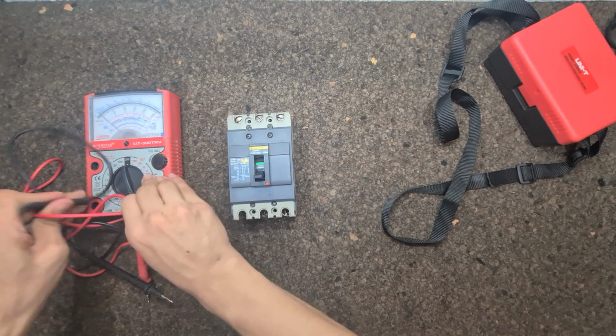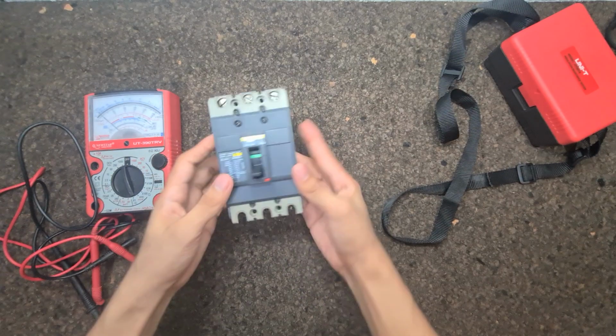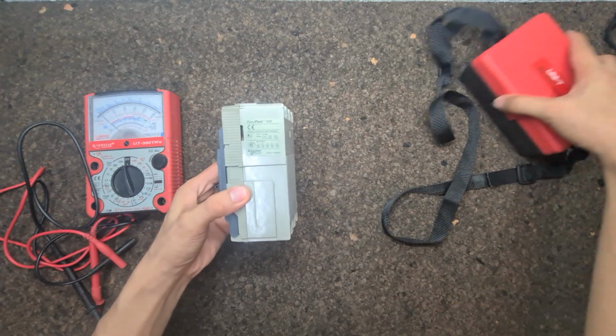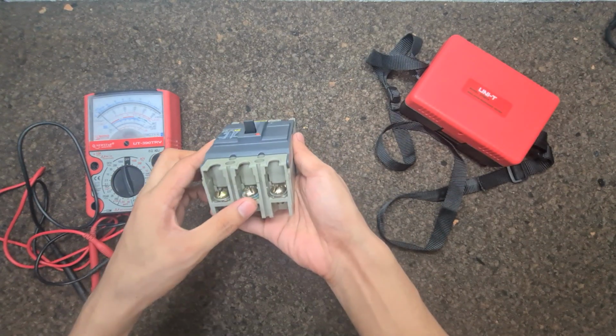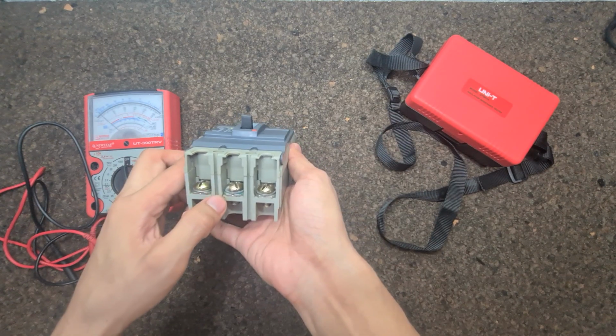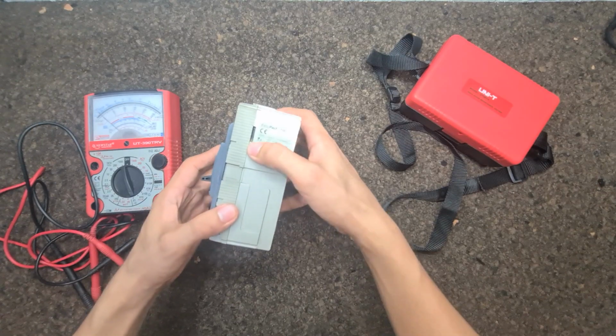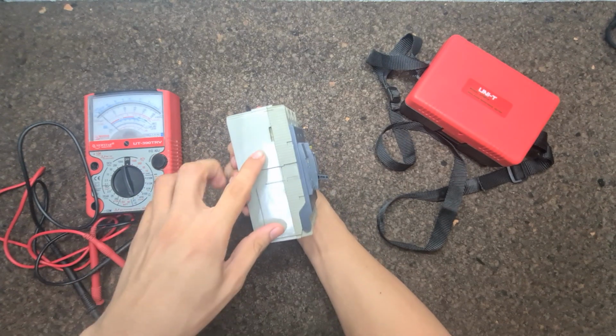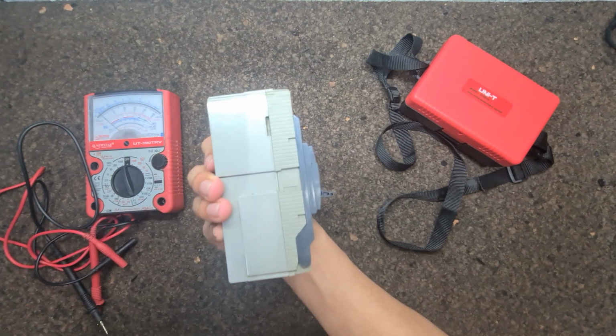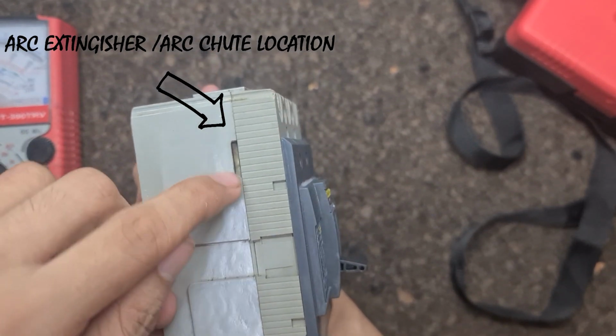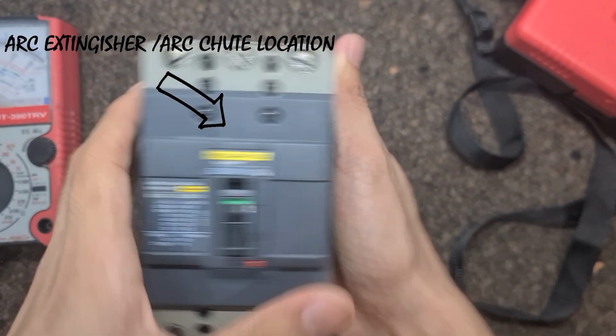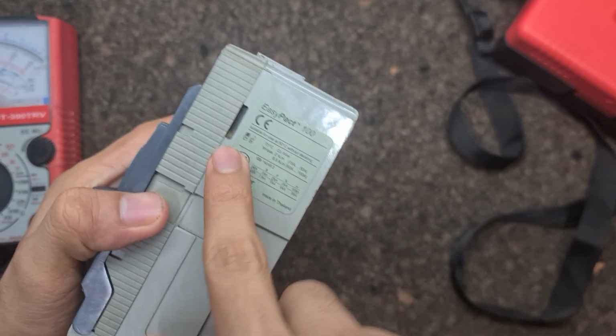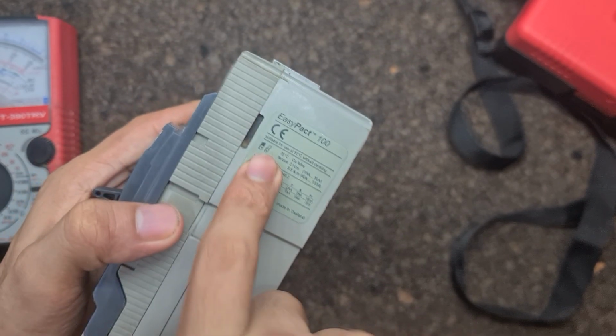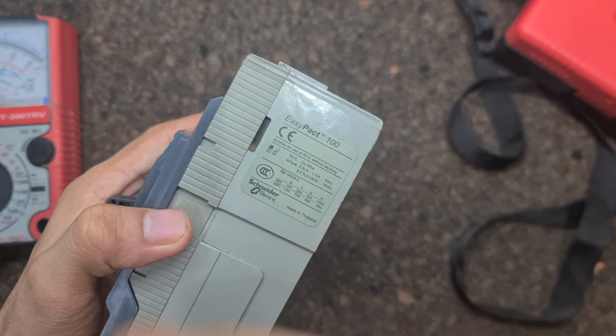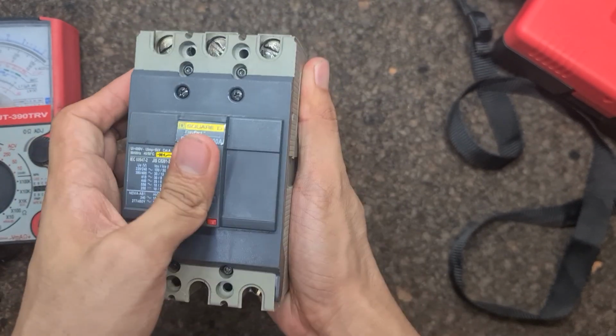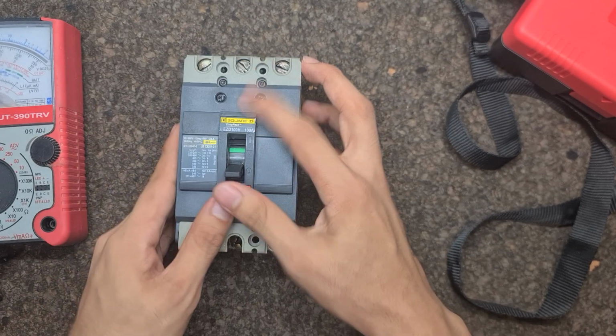Before going to testing, let's have a visual inspection. One sign of a circuit breaker, specifically a molded case like this, that encountered a fault is in the arc extinguisher portion, which has a sign of dark color compared to the actual body color, or like dirt, known as an arc burn mark, which indicates a short circuit fault or arcing inside the breaker occurred.